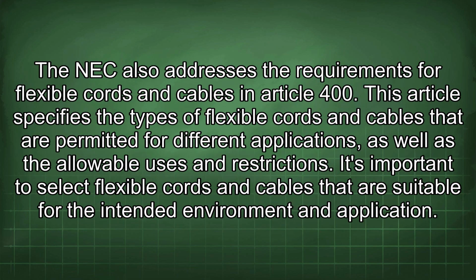The NEC also addresses the requirements for flexible cords and cables in Article 400. This article specifies the types of flexible cords and cables that are permitted for different applications, as well as the allowable uses and restrictions. It's important to select flexible cords and cables that are suitable for the intended environment and application.